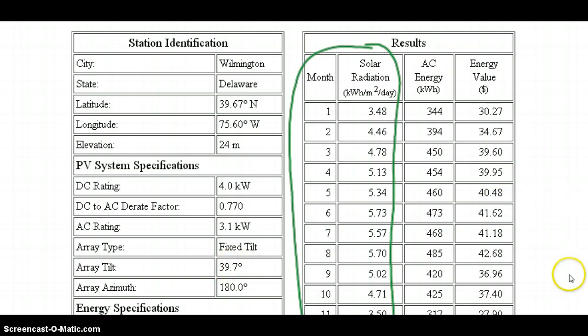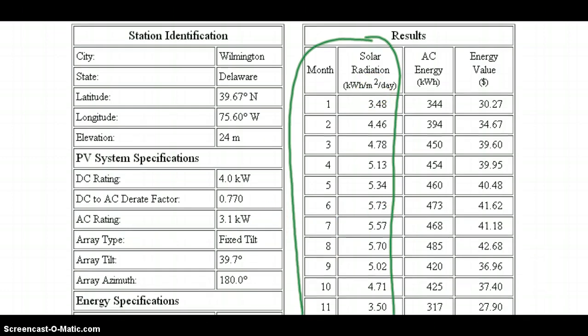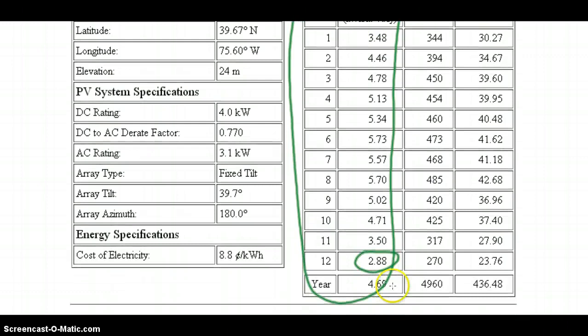So what you do, is you design for what's called the worst month. So we're going to look at which month the solar radiation is the lowest. And in this case, it's December, and it's 2.88 sun hours. So now we need to remember what sun hours means.